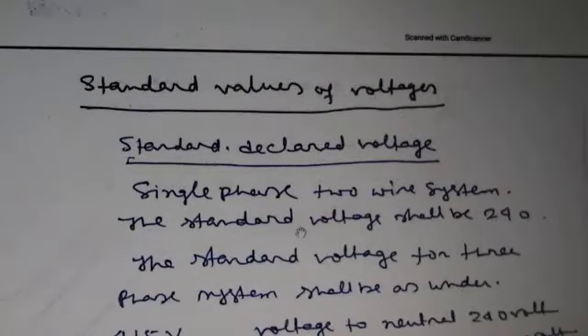Now, standard values of the voltages. For medium and low voltage distribution systems, the originally recommended standard value of normal voltage is 230 volt for single phase and 230 by 400 volt for three phase systems. However, during 1959, to align with IEC recommendation and due to the economic advantage, the value of 240 volt for single phase and 240 by 415 volt for three phase has been adopted.